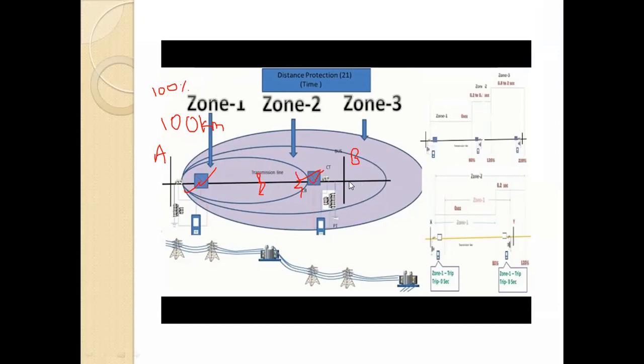From the first zone, remaining 20%, plus from second zone, plus after AB, the remaining transmission line. Remaining transmission line means remaining 20% line is taken for zone 2. So the total setting becomes what? Total setting is 120% for this second zone.